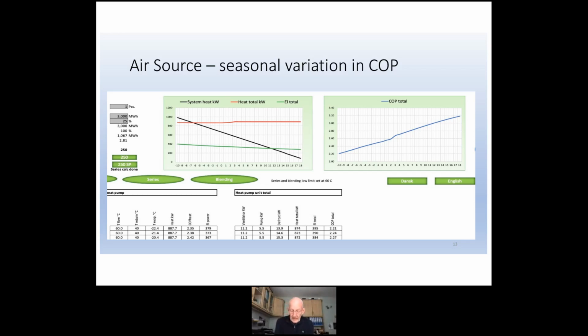The kink in the middle, by the way, is the defrost cycle, which is required at temperatures just above freezing. When we take 5 degrees, for an example, out of the air, we can very easily freeze the equipment. So that kink is the energy that we have to use to defrost the equipment without having any impact on the output. By the way, we defrost the evaporators in sequence, but that has a negative effect on the COP, and it just is shown in a kink in the middle. So we've got a much more variable COP. This one happens to run from 2.2 to 3.2, totally dependent on air temperature.